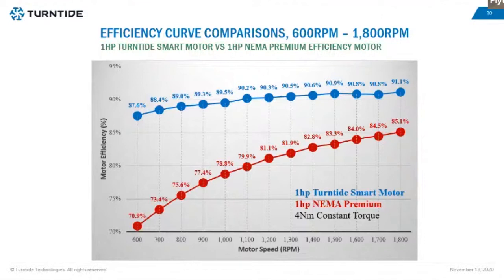So you're not operating the induction motor at rated conditions, rated speed and rated torque, and the efficiency drastically reduces, going from 85% to 70%. As you can see on the top curve, blue, that's our Turntide smart motor system.